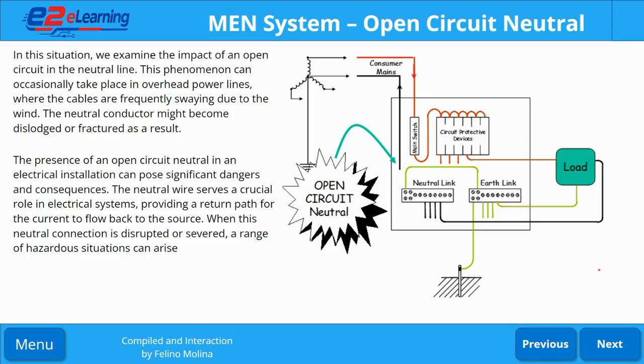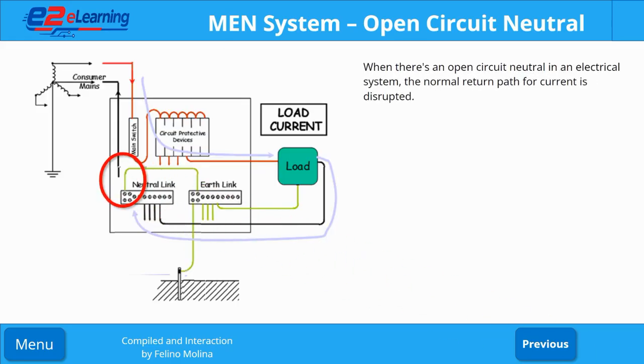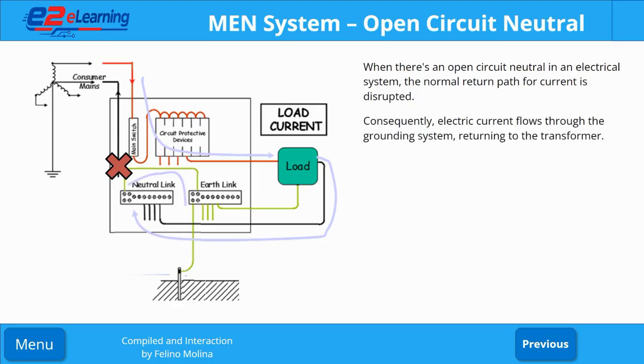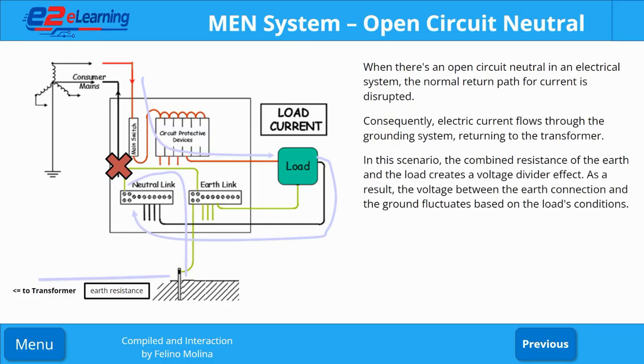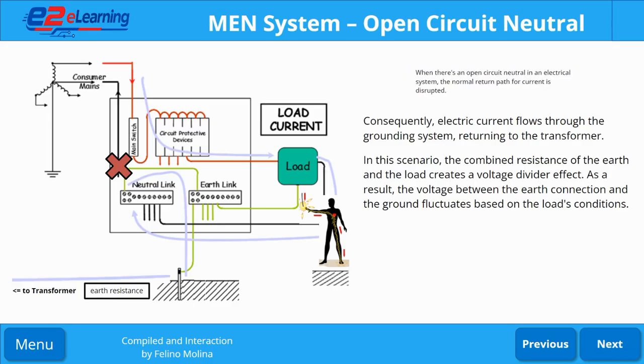The neutral wire serves a crucial role in electrical systems, providing a return path for the current to flow back to the source. When this neutral connection is disrupted or severed, a range of hazardous situations can arise. When there's an open circuit neutral in an electrical system, the normal return path for current is disrupted. Consequently, electric current flows through the grounding system, returning to the transformer. In this scenario, the combined resistance of the earth and the load creates a voltage divider effect. As a result, the voltage between the earth connection and the ground fluctuates based on the load's conditions.